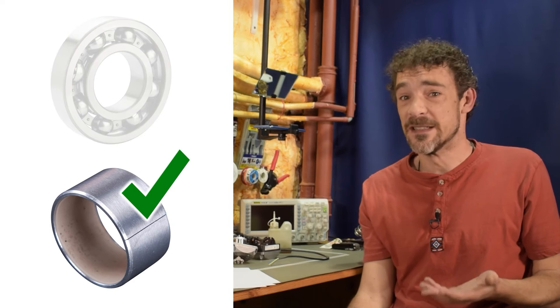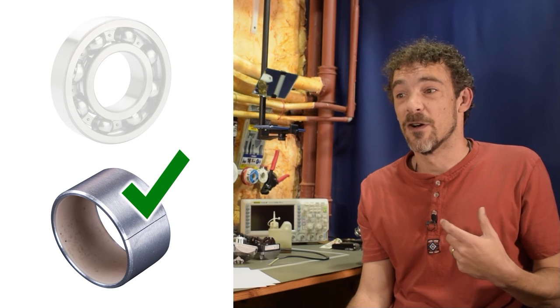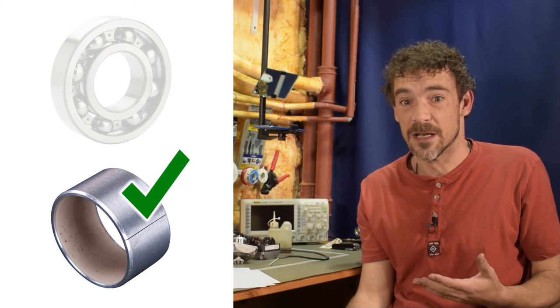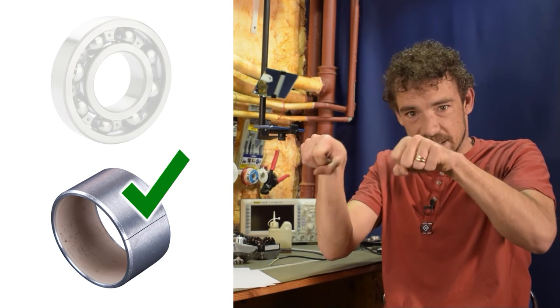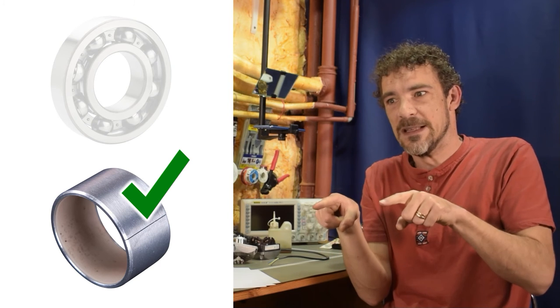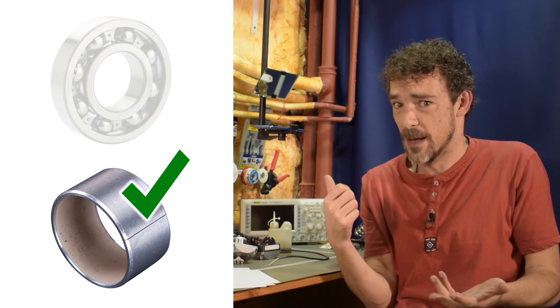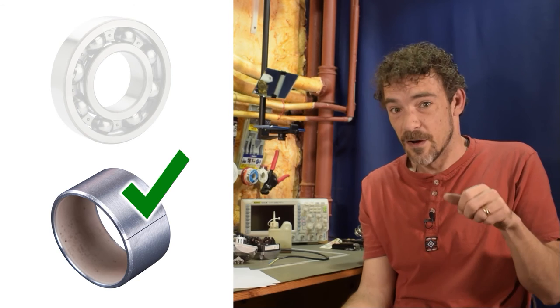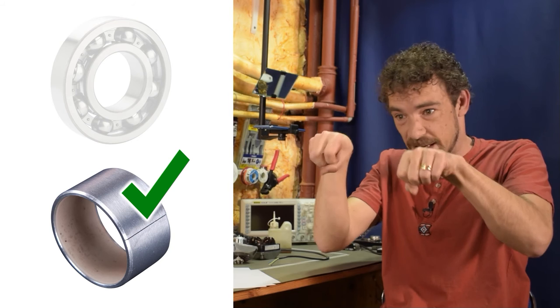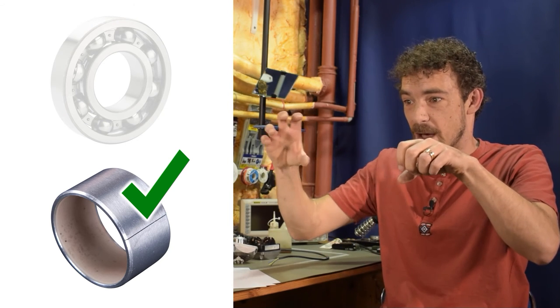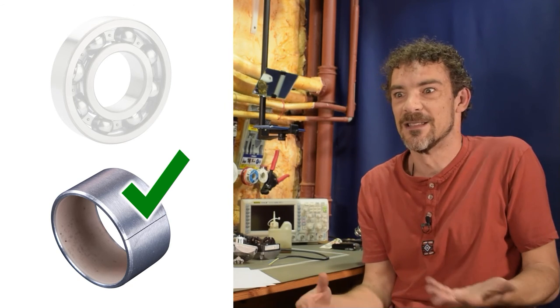And one of the reasons that type of bearing is used is even though it's higher friction, you machine the bearing and you machine the axle very, very, very tightly. Sometimes there's little notches on the bearing that hold a little lubricant, but basically you just got your bearing, you got your shaft, you stick the two together and there you go, right? You put a little light machine oil on sticking together and it's going to last for quite some time. The main benefit of using a sleeve bearing is not only is the fan motor going to be far less shaky, less vibration, because if you have a sleeve that's holding that rotor on two ends like that, it's not going to be able to vibrate that much. That also means that if you have it say like this one, using it as a cooling fan for a compressor running on top of a refrigerator, which vibrates a lot, the vibration of the compressor is not going to damage the fan over time because it's held by these big honking sleeves, the axle is held and it can move this way and that way a little bit as it spins, but it's not going to like move in all kinds of directions and become damaged and wear the bearing because the bearing is very solid.